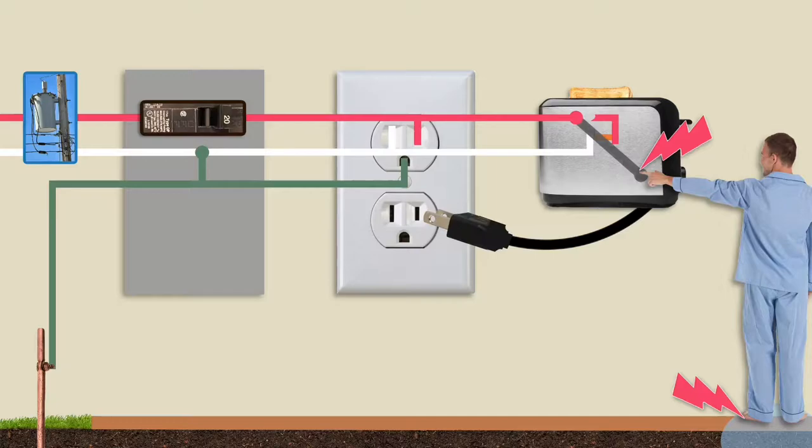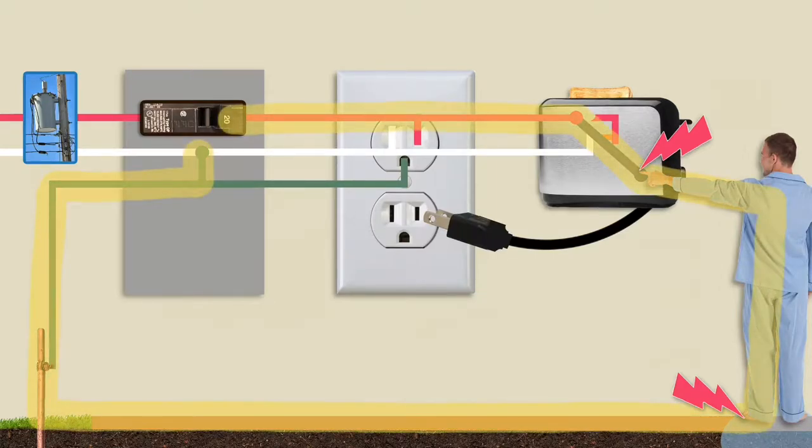That's because the person completes the connection between the hot and neutral line through the earth ground. And unfortunately, because the resistance of the earth path is so high, the circuit breaker is unlikely to trip. This is extremely dangerous because, as we've learned, when high voltage passes through a person's heart, it can stop beating.